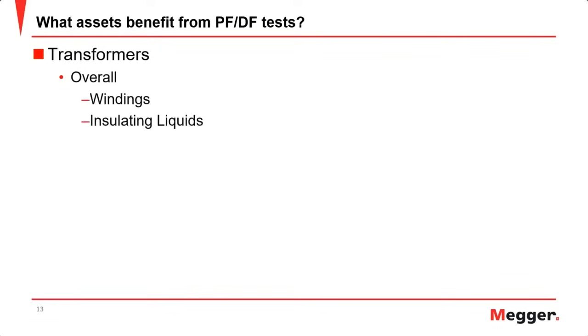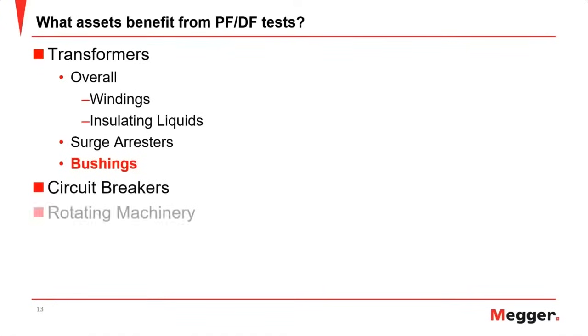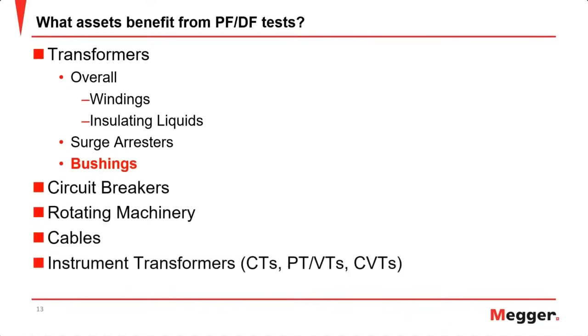And what assets benefit from these tests? Of course, transformers, looking at the overall condition of the windings and of the insulating liquids, again, that's going to be your oil or your FR3. You can also look at surge arresters. And then, of course, what we're here to talk about today is the bushings. But power factor testing goes beyond just transformers. It can also be used with circuit breakers, rotating machines, cables, and instrument transformers like CTs, PTs, and CCVTs.